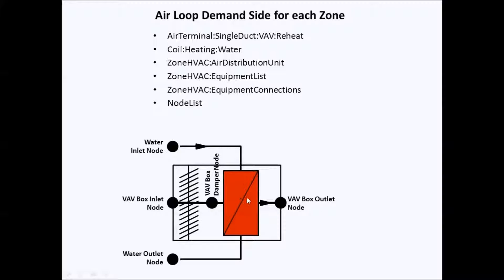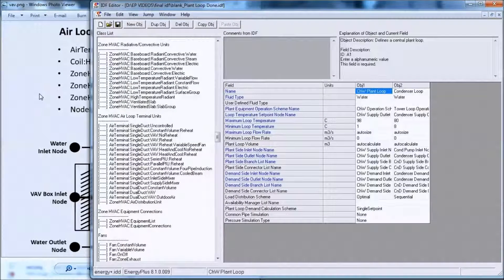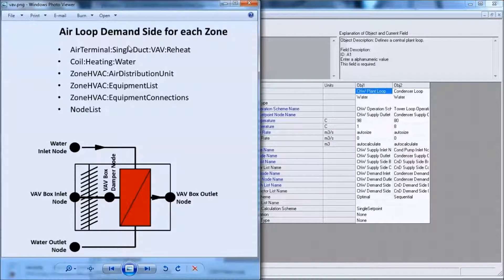After the damper there is a VAV box damper node, then a heating coil, and a VAV box outlet node. To make a VAV we have to create objects in this order: air terminal single duct VAV reheat, then a heating coil for the reheat, then the zone HVAC objects — air distribution unit, equipment list, and equipment connection. The node list is not required when there is one VAV in a zone but is required when there are two VAVs in a single zone. I'll demonstrate one VAV for a zone, then two VAVs for a single zone, then fast forward through the rest.